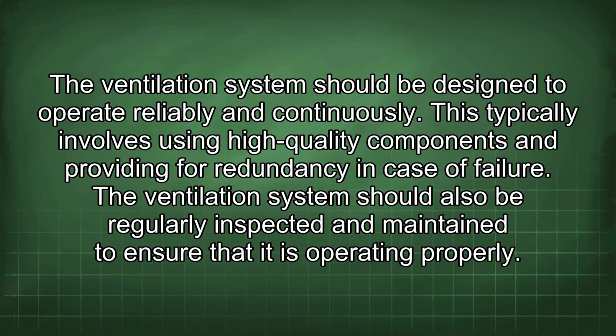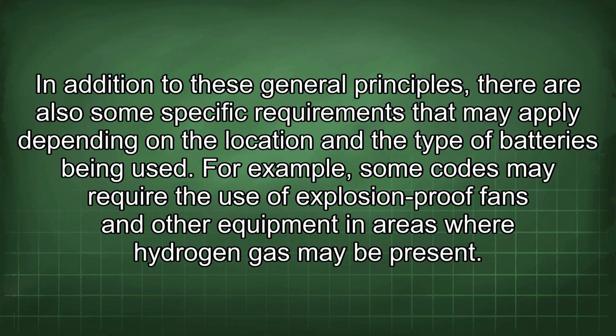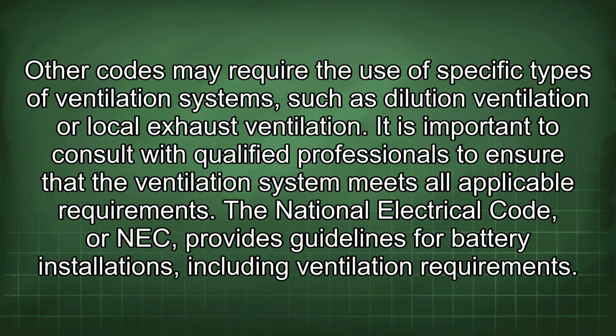The ventilation system should also be regularly inspected and maintained to ensure that it is operating properly. In addition to these general principles, there are also some specific requirements that may apply depending on the location and the type of batteries being used. For example, some codes may require the use of explosion-proof fans and other equipment in areas where hydrogen gas may be present. Other codes may require the use of specific types of ventilation systems, such as dilution ventilation or local exhaust ventilation. It is important to consult with qualified professionals to ensure that the ventilation system meets all applicable requirements.